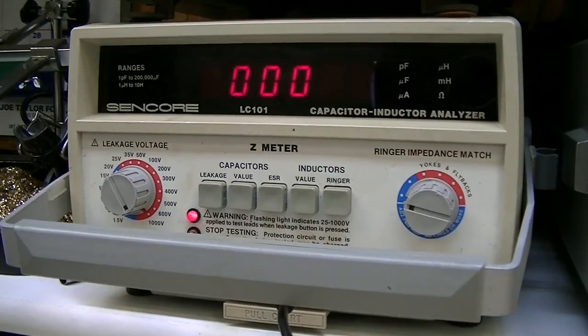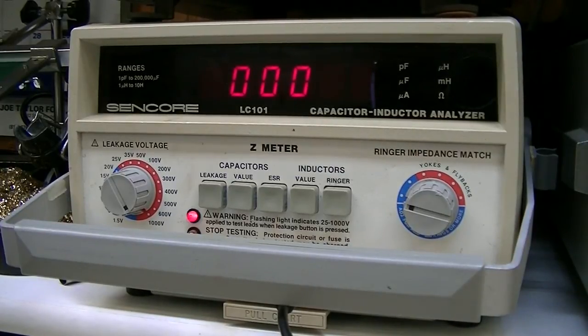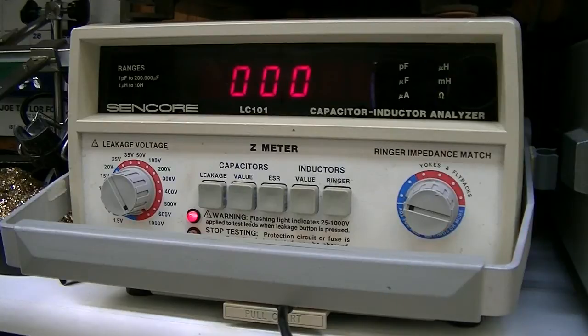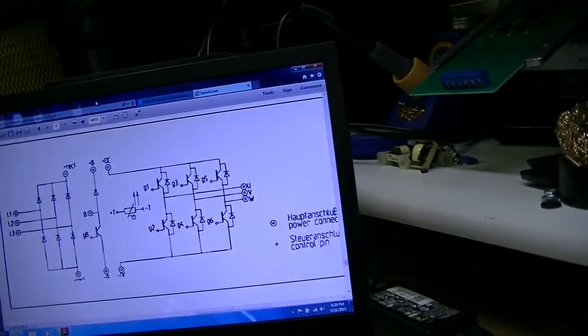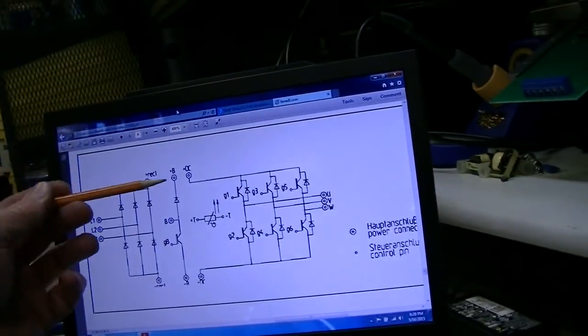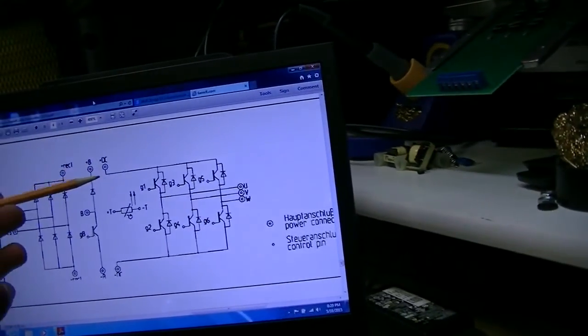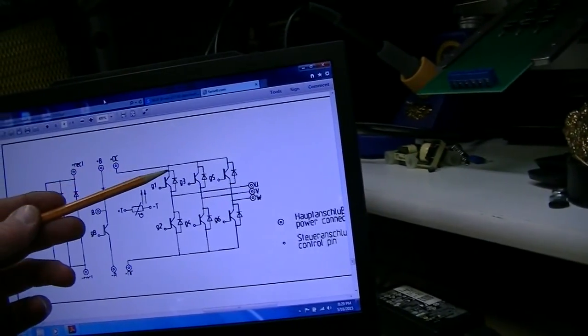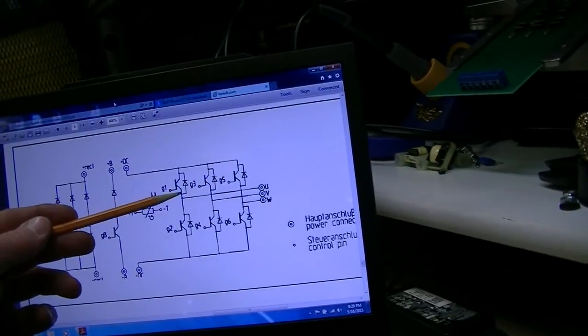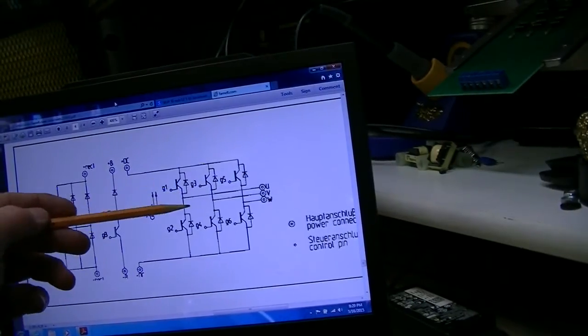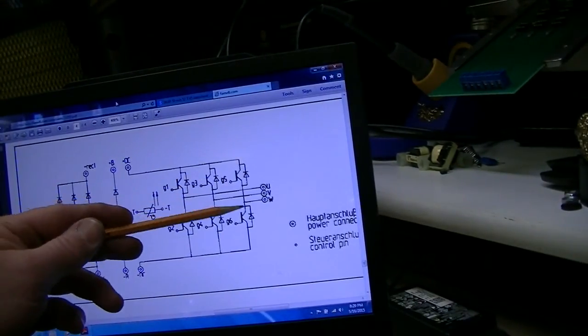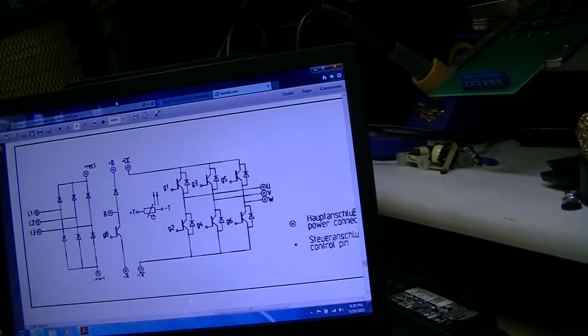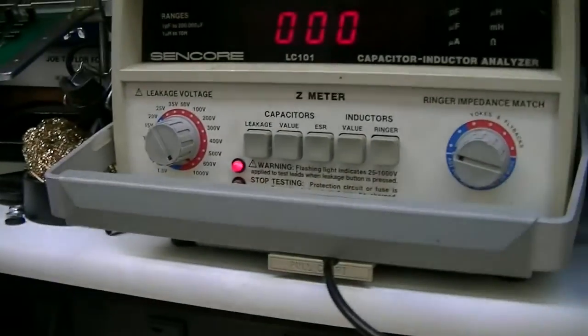Okay, so I'm now testing the high voltage blocking on the IGBT. I've got the positive lead on the so-called DC plus. And then we're checking the blocking voltage of each one of these. So, we'll see what we get there.